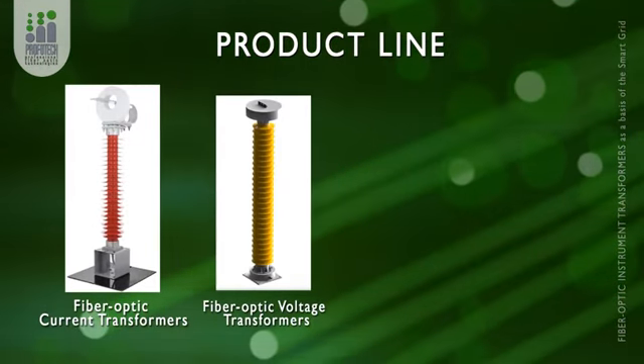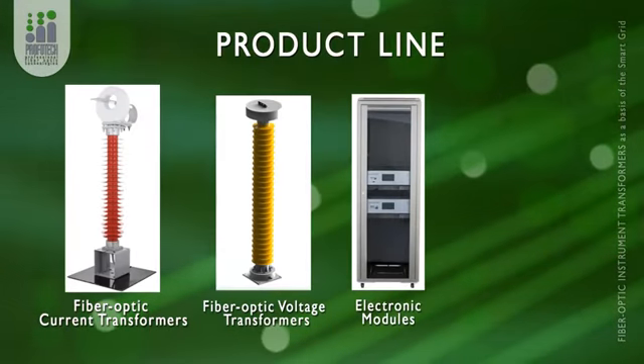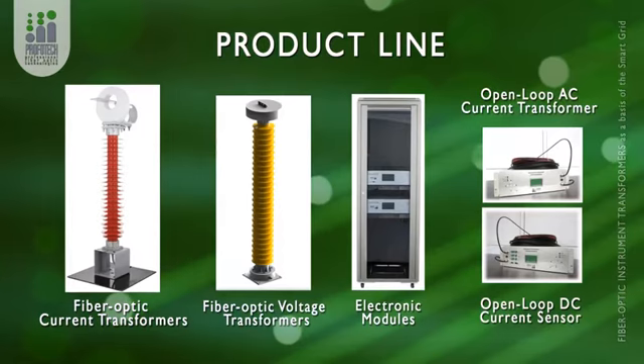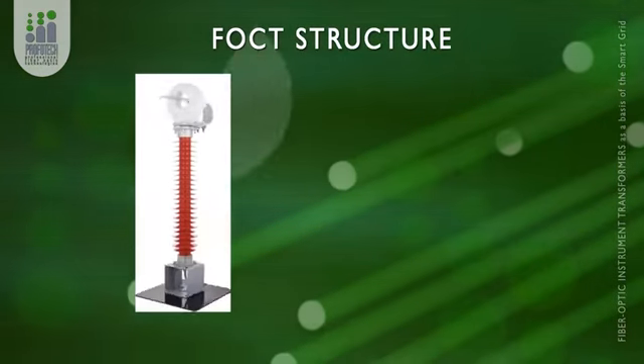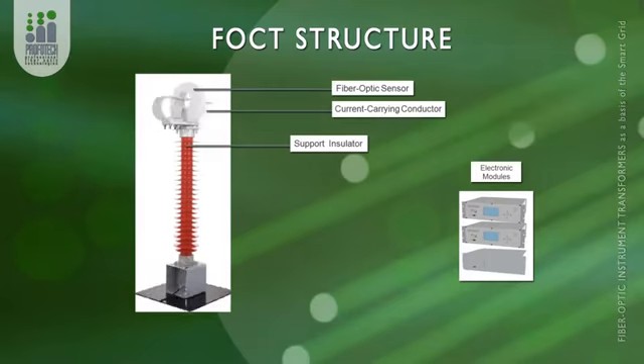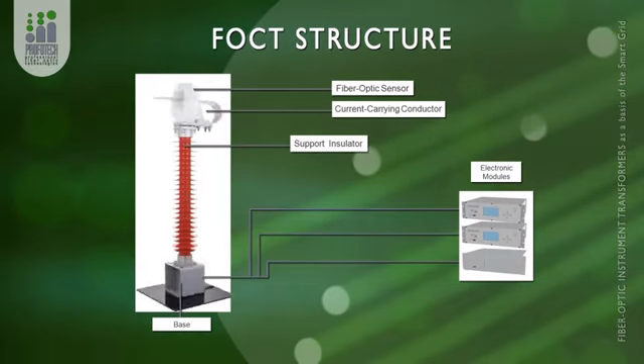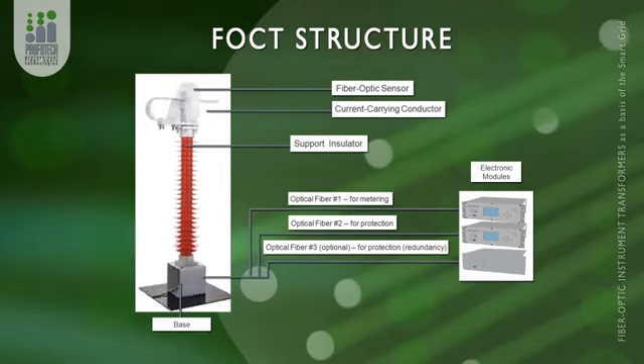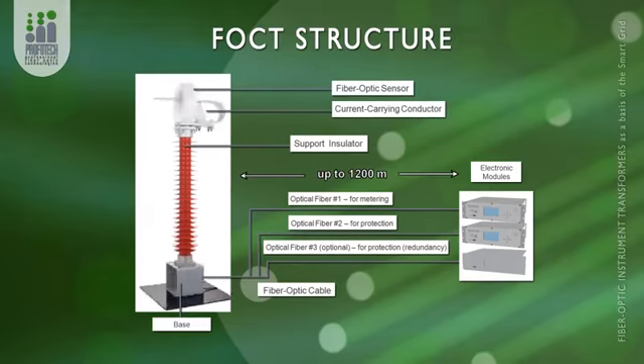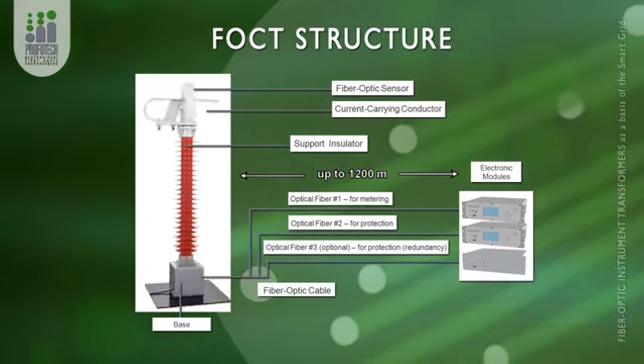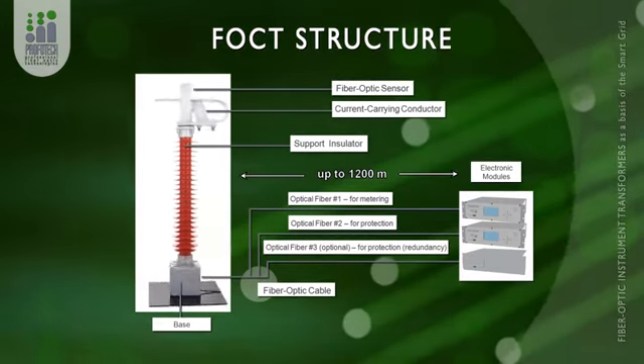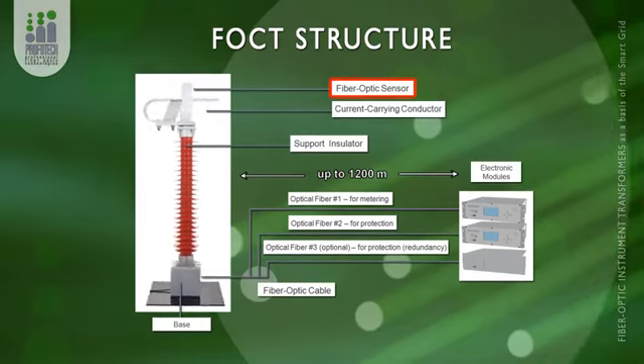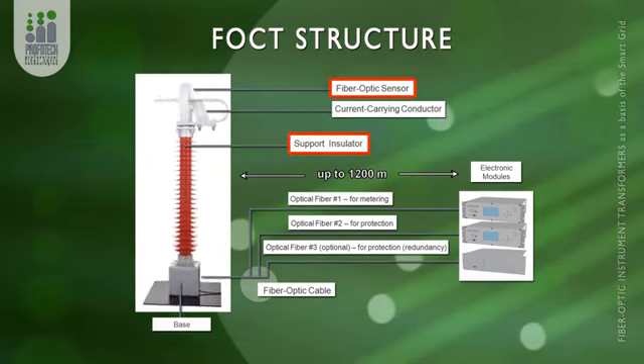So, our product line of Profotech is presented on the slide. The fiber optic current sensor, the fiber optic voltage sensor, electronic interfacing modules, and the open loop AC-DC current sensor, which I will describe a little bit later. Starting with the fiber optic current sensor, it looks like the conventional instrument transformer, with the only difference being that it is much lighter in weight. This instrument, for only 110 kilovolts, is only 70 kilos compared to 500 kilos for the conventional instrument transformer. The difference is due to the optical sensor, which is located at the top of the support insulator.